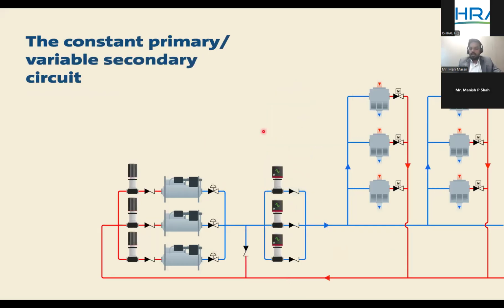And same thing, we still see that constant primary and variable secondary is also a more adaptable system, even in data centers. And even with that concept, distributed pumping or coil pumping can be very well done. So the design philosophy is very simple. The primary pump is fixed speed, and the primary pump is designed to overcome the friction only on the production circuit, which is the primary circuit. And we have centralized secondary pumps. So from the decoupler, the centralized secondary pump will push the water commonly to the multiple loads, and we have a balancing and modulating valve which balances and modulates the flow based on the change in the load. Pretty simple.